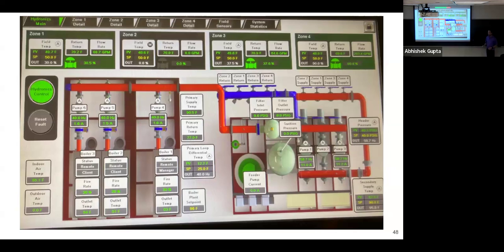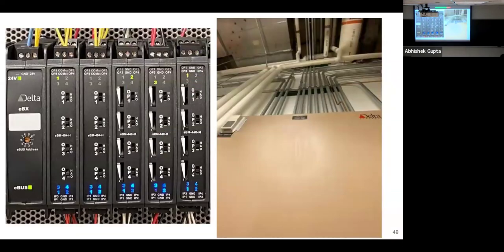Right, so in this case it's likely a default or mismapped value. Yeah, or they haven't hooked it up, maybe it's still in construction and they haven't hooked up the outside air sensor yet, but something we would highlight in the risk assessment: this system's running right now and there's no outside air reference. This one's a little bit harder.